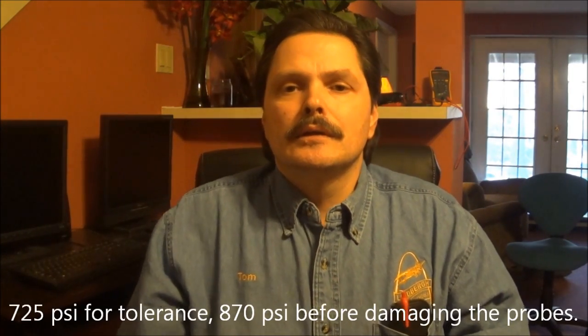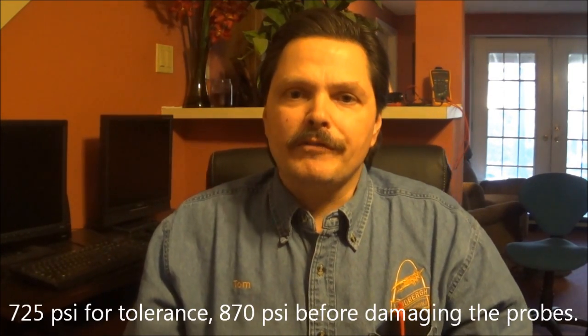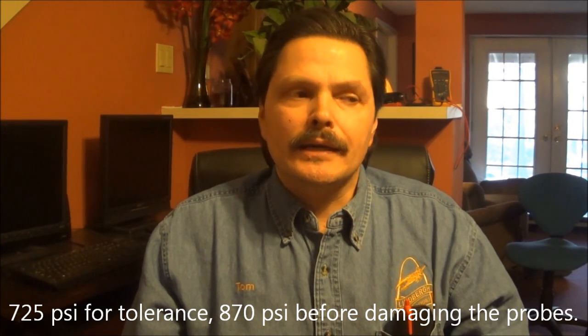Well, I looked online and all the specifications show that they're all the same. They have a 0.5% tolerance of full scale. I called Testo today to verify that, and they are rated from like 0 to 725 pounds PSI. So 0.5% of that would be 3.625 PSI plus or minus. That's what they're rated for.